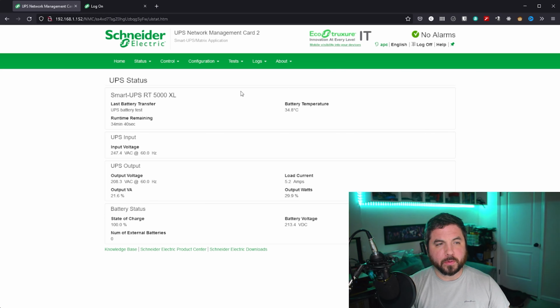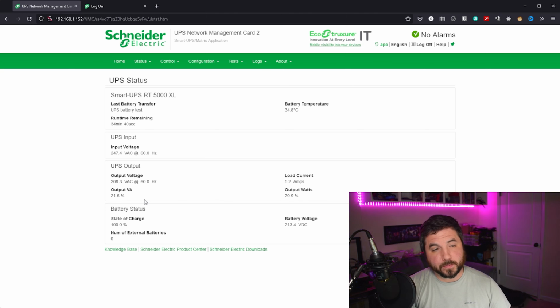But essentially, when you are logging into your UPS, you have this UPS status, and you can see runtime remaining, when it was last transferred to battery, the temperature, the input voltage. I'm running on 240 or so, somewhere between 240 and 248 volts AC, and the output voltage is 208 volts at 60 hertz. Current load is 5.2 amps. And the output volt amps is about 21.6%, and the output watts is close to 30%. The batteries are brand new and they're fully charged, and you have the battery voltage, which is a DC voltage.